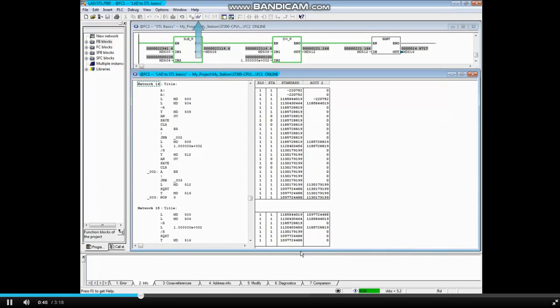Notice here, monitoring is turned on. If checking for overflow is not important to your calculation, the code can be greatly simplified. The 7 lines of code shown in network 15 of the bottom block will perform the same calculation without overflow checks as the 26 lines of code from network 14.